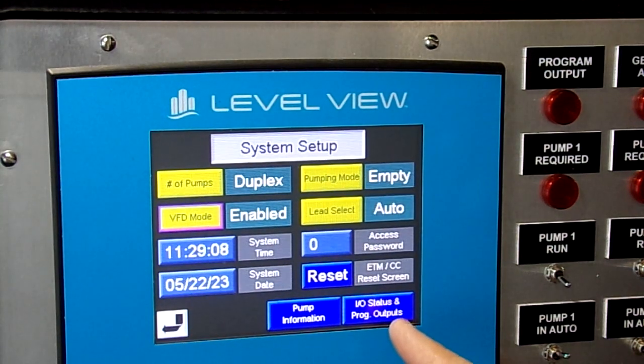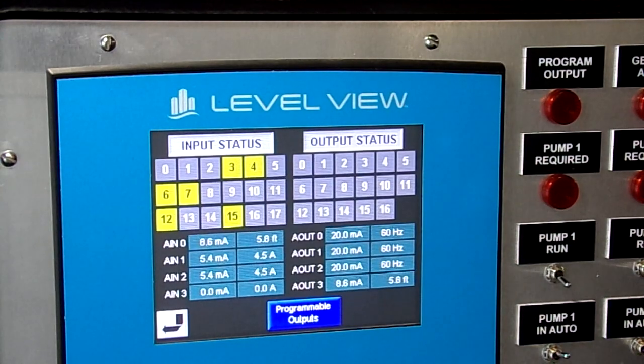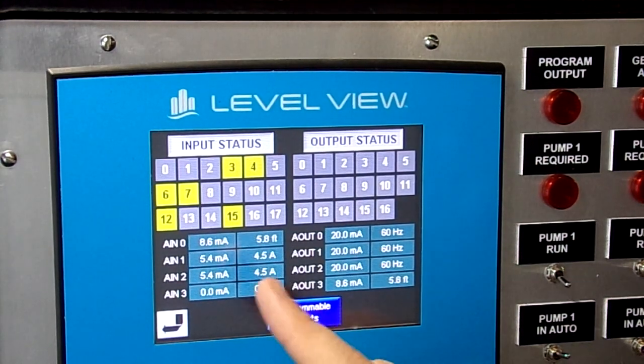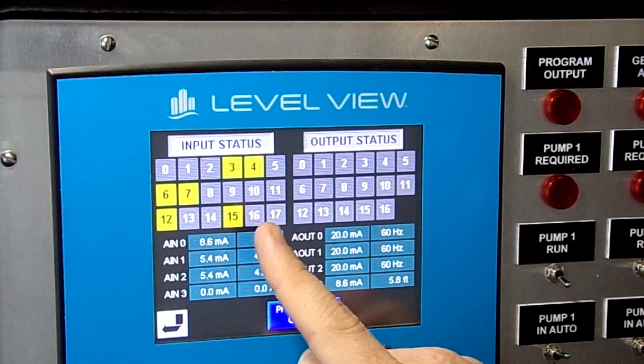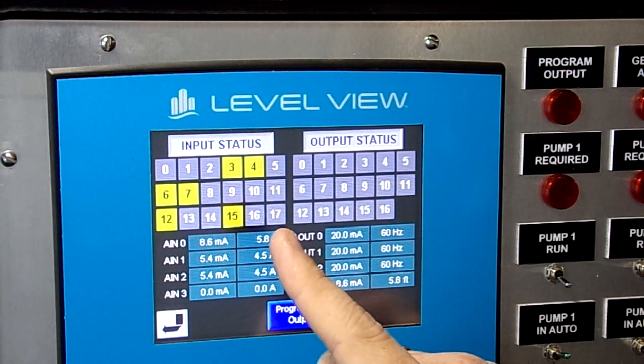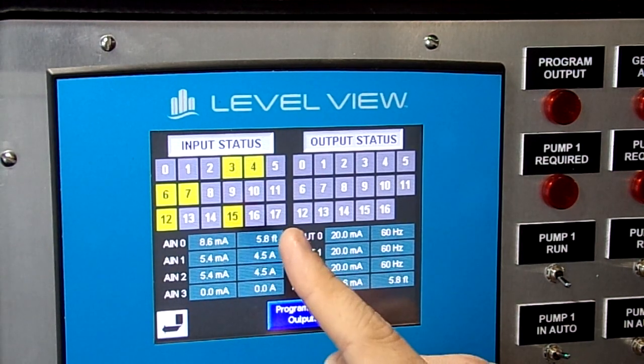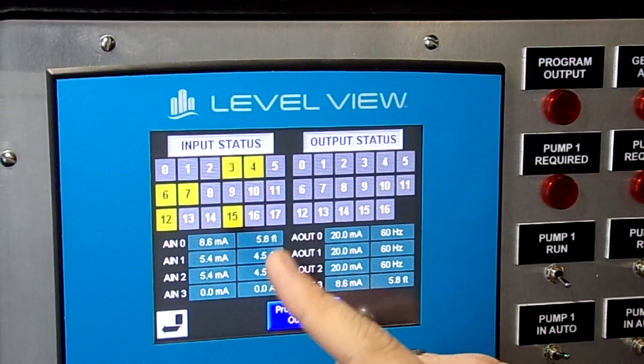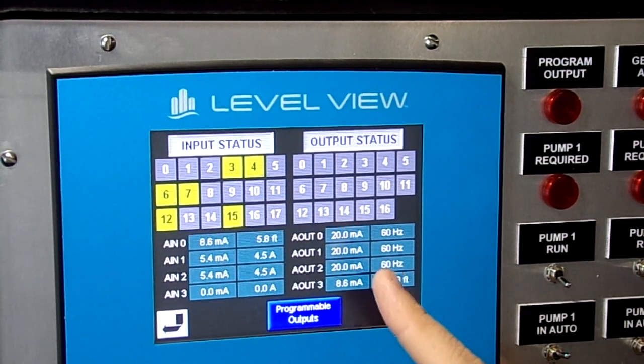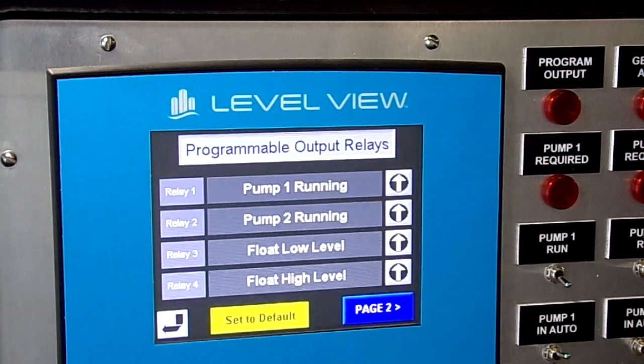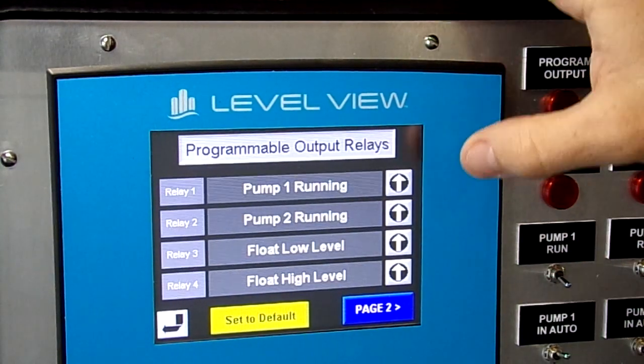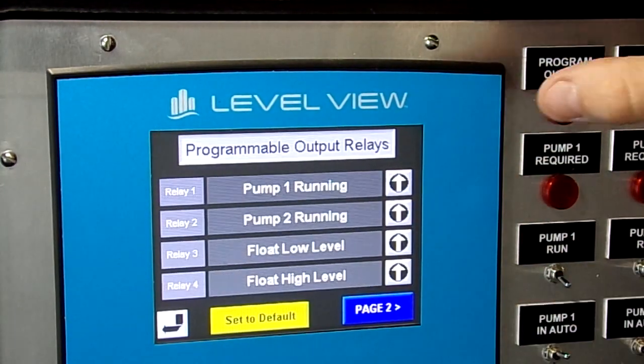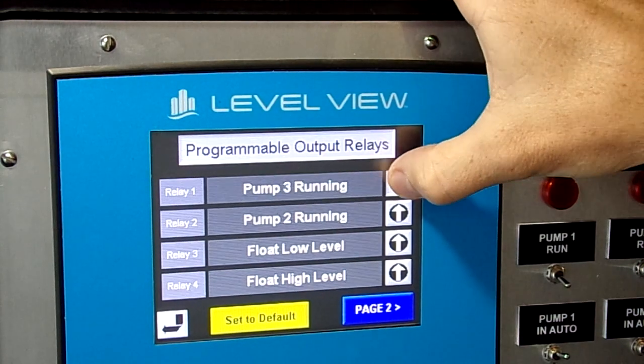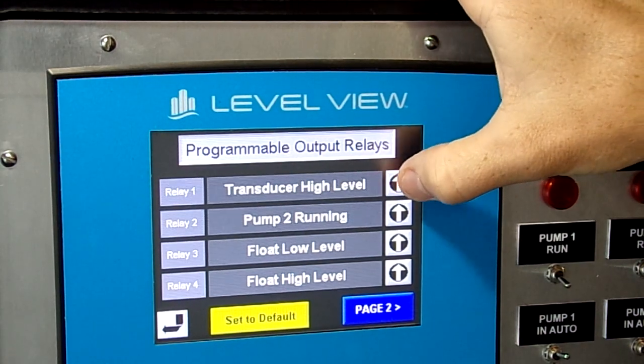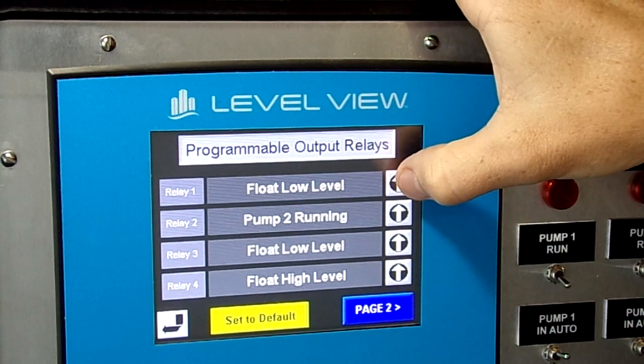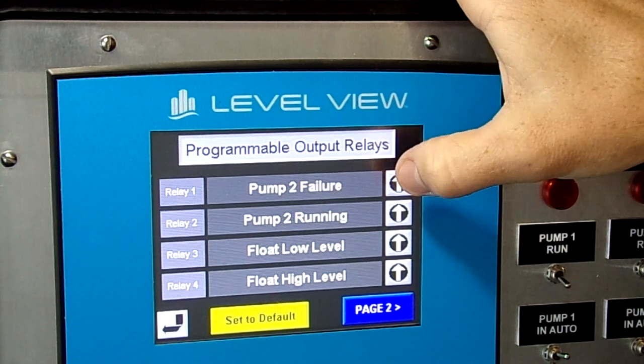The I/O status and programming outputs. If you have questions and you want to contact our factory, this will give you what inputs and outputs are active currently. This will help us identify whether we have good inputs or bad outputs, so we can be tested with the meter. We also have the ability to come in here to go to our programming outputs, click on this, and with 7 relay outputs, we can monitor any desired failure that we want to follow.